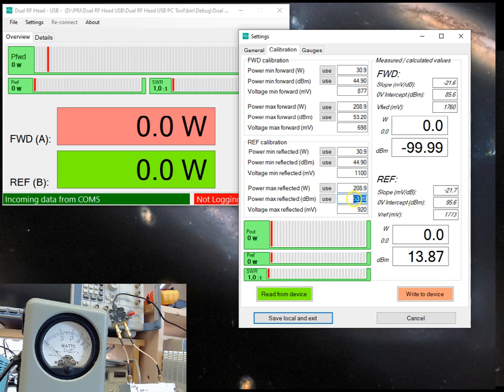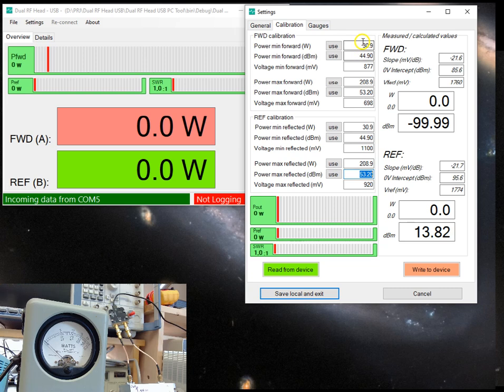Otherwise it will not know what is correct, so the dBm values will always be used. The easy thing is, as I did up here in the forward, type in 31 watts, press use, type in 210 watts, press use when you have low and high power on the transmitter. That's it. Then turn around the directional coupler and do the same for the reflected port. That's it, so all the data are in the device.